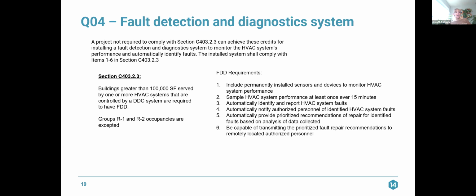Q04, fault detection and diagnostics. Sorry. So a project that is not required to comply with section C403.2.3 can achieve these credits for installing a fault detection and diagnostic system to monitor the HVAC system's performance and automatically identify faults. The installed systems shall comply with items 1 through 6 in section C403.2.3. So section C403.2.3, there was an update to this section from the 2021 IECC.